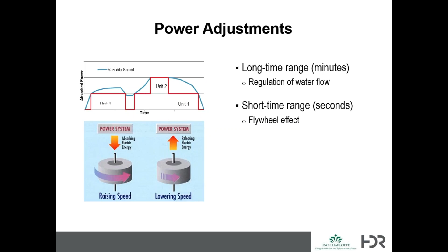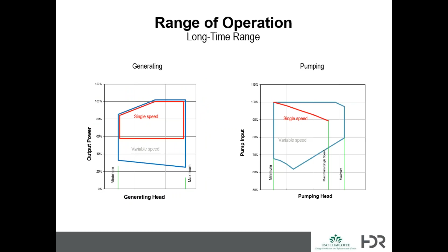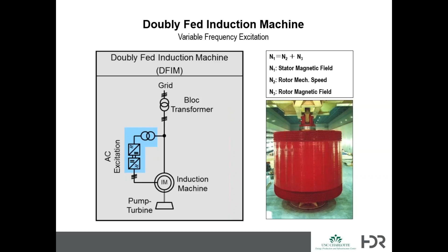It allows you to provide frequency regulation and incremental and decremental reserves, moving up and down when you're pumping, which is exactly what you need when you have excess supply from wind and solar. I've never seen a gas turbine work backwards to do that. And then you have a much broader operating range. Applying these capabilities for our clients and these engineering challenges is what our team does. I won't get too detailed on what a doubly fed induction machine is. It's just a taller generator. The wet side, the turbine side, is almost identical, but you have much different generator capability. ABB here in town designed some of these machines on the generator side.